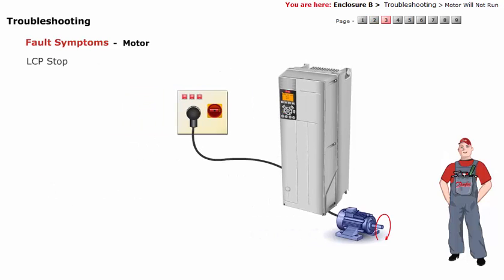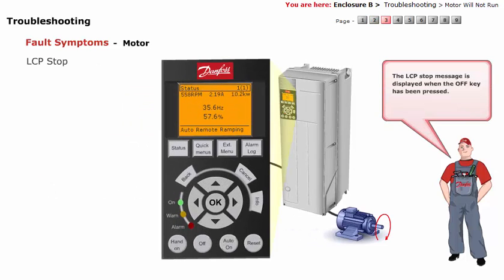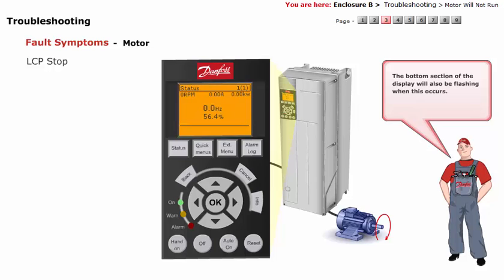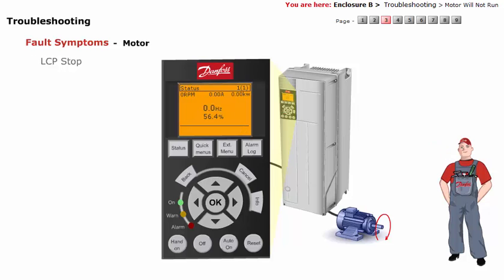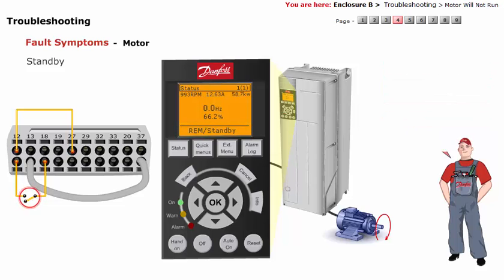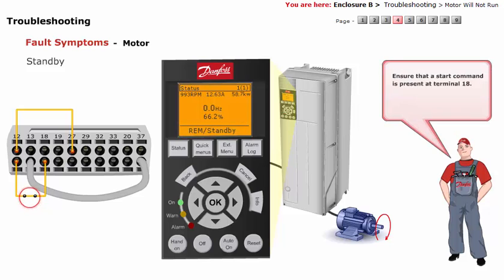LCP Stop: the LCP stop message is displayed when the off key has been pressed. The bottom section of the display will also be flashing when this occurs. Standby: the standby message is displayed when there is no start signal at terminal 18. Ensure that a start command is present at terminal 18.